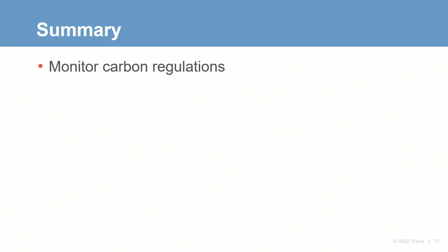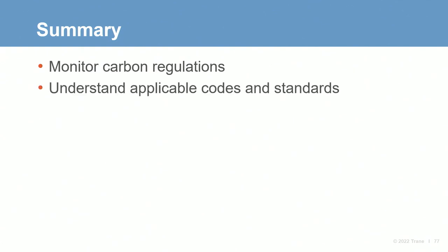Simulation software capability continues to evolve to support electrified heating system analysis and will also be covered in a future E&L. This E&L covered air-to-water heat pump-based systems and provided guidance for evaluating loads, sizing equipment, and configuring plant layouts. In summary, key elements to successful low-carbon applications include monitoring carbon regulations affecting your site, and understand applicable codes and standards. Know your building loads and leverage coincident, non-coincident, or dominant loads in system design.